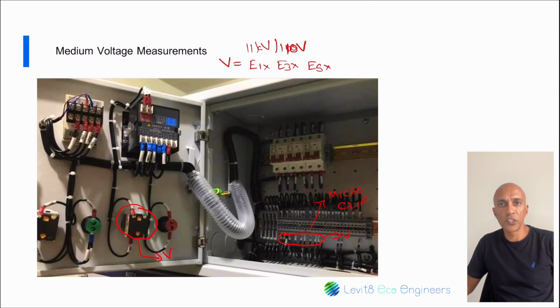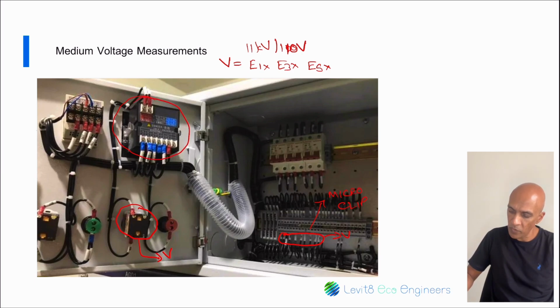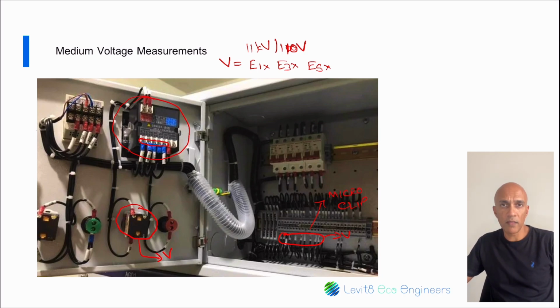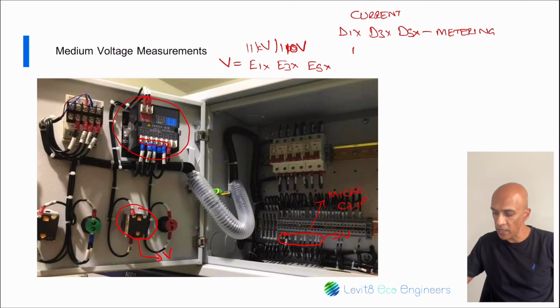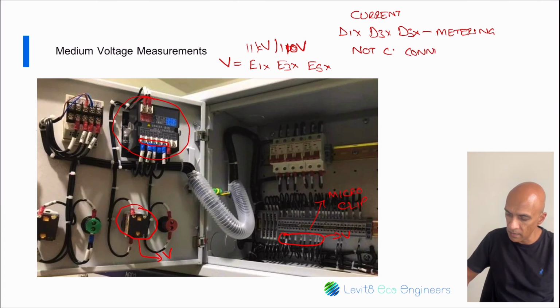Now, for current measurements, there is no other choice but to use transducers, because the only place current readings can be obtained is from the secondary of the metering CTs inside the medium voltage panel. So if you have panels, M meters, then you would typically connect, and let's assume this is the M meter, you would typically connect your current transducers here. So this is typically behind the M meters, and they would be labeled D1X, D3X, and D5X. Note that the connections C1X, C3X, and C5X are for protection CTs. It is better to measure on the D connections for better accuracy. So metering should be D label, and then your protection would be C labels.